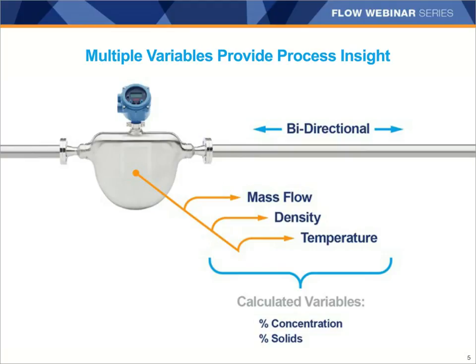Here you can see a picture of a Coriolis flow meter, and I'm sure these are really familiar to a lot of you on the call. Coriolis meters are well known for providing accurate mass flow measurement. However, they also measure density of the process fluid, and they have built-in temperature measurement. Using the density and the temperature measurements, they can calculate and output other process variables like percent concentration or percent solids. The mass flow combined with density can also be used to output volumetric flow rates through the line.